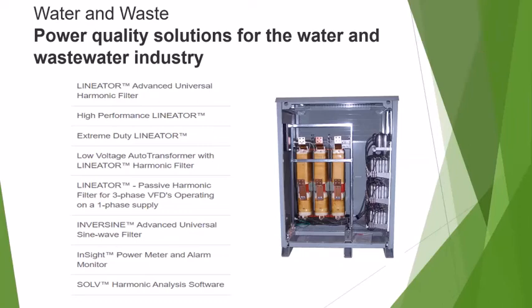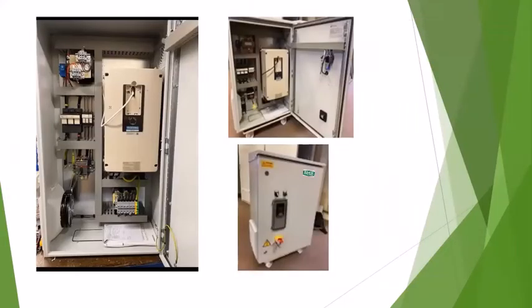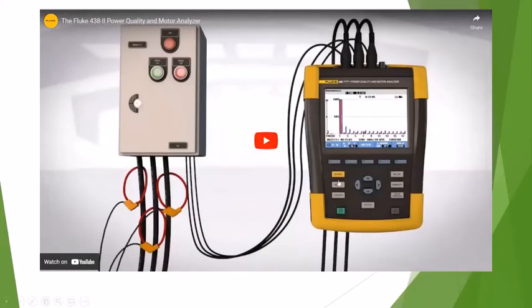Yeah, and so what I always recommend is that they do go back and put the power analyzer on it, so we can see what we're actually dealing with. You'll hear a lot of them talk about point of common coupling, which in the United States would require you to stay in IEEE compliance. But point of common coupling is actually out at the transformer, at the primary side of the high voltage. That's what the power company is worried about, their circuits, their lines. And so that's what they put it as.